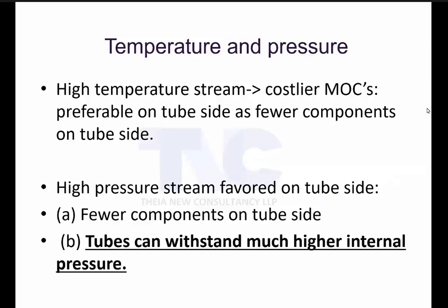Higher temperature. Remember, when there is a high temperature, you need a higher MOC. When you go for a costlier MOC, is the preferred side shell or tube? Always tube. Because a good designer has to design an exchanger which is economical. So whenever you see very high temperature exchangers, generally those process streams are sent to the tube side, because the tube side has fewer components, that is why I send it to the tube side.